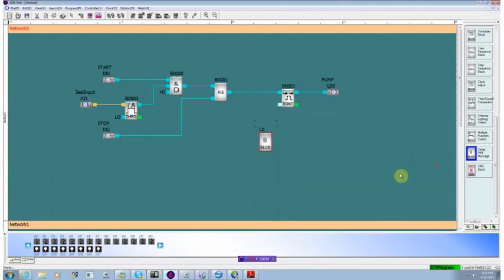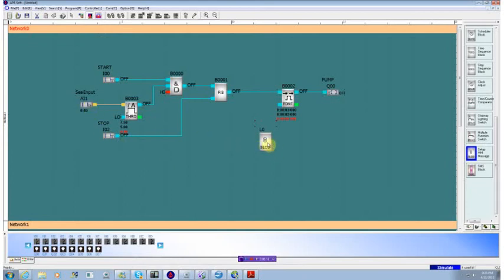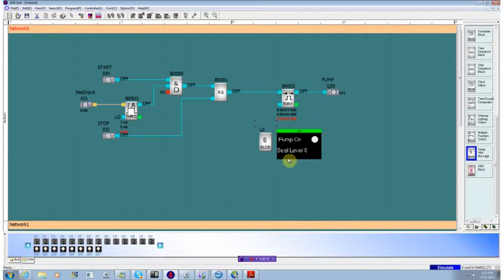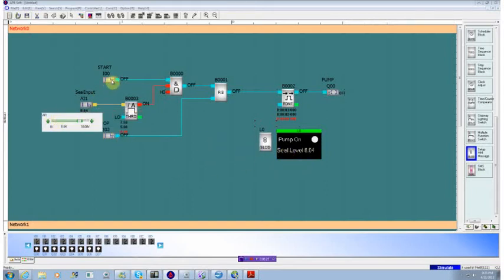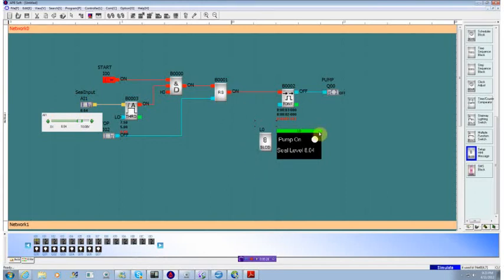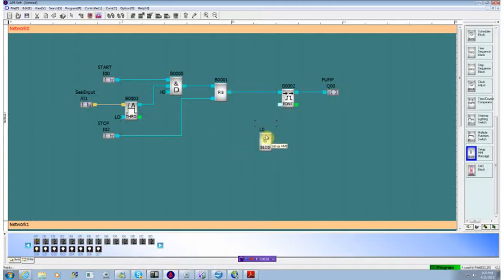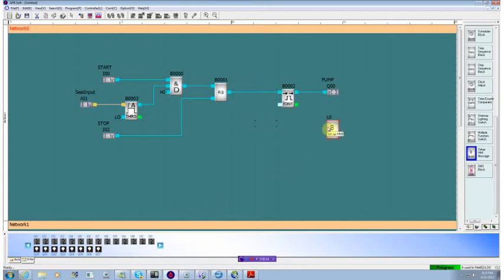And we'll have these numeric values filled in when the application is actually running. So we now have a reading of our seal level, the pump on or off. And if we select OK, run our simulator again. First thing we'll do is we'll click on this and this shows us the display as it would be on the LCD itself. When we run our analog input level up, we see that it matches over here. And when we start our pump, after three seconds we'll see that the pump comes on. So we now have the human operator screen, human interface screen up and running, and the operator can see the status of the system.